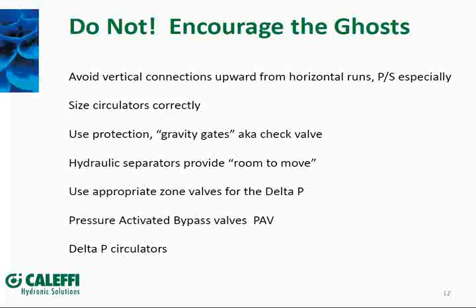The thing to do is avoid piping configurations that would induce thermal migration when putting the system together. Also, size circulators correctly — sometimes what we think is ghost flow might be an oversized pump actually pushing through a zone valve. A high-head pump can push through a circuit when the zone valve can't shut off tightly against that delta P.